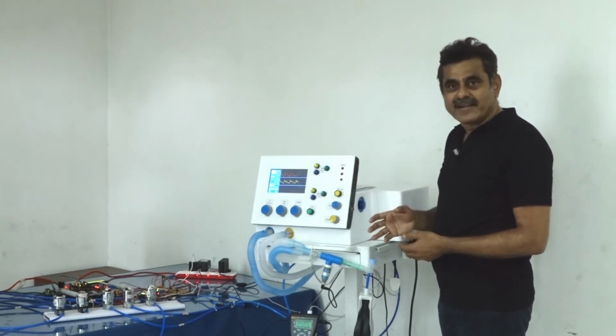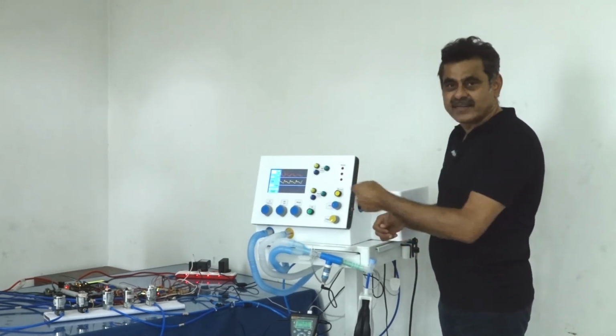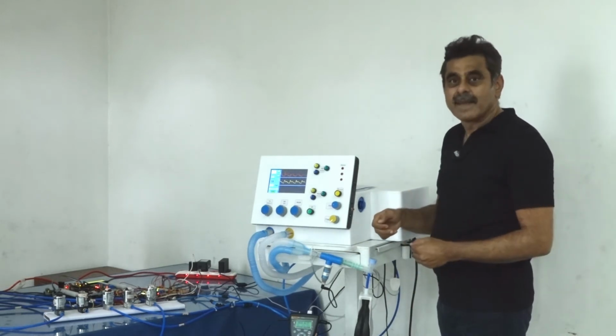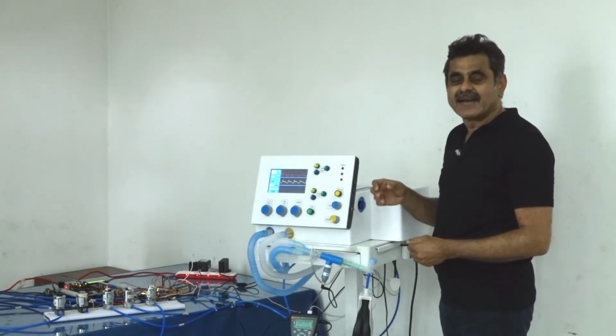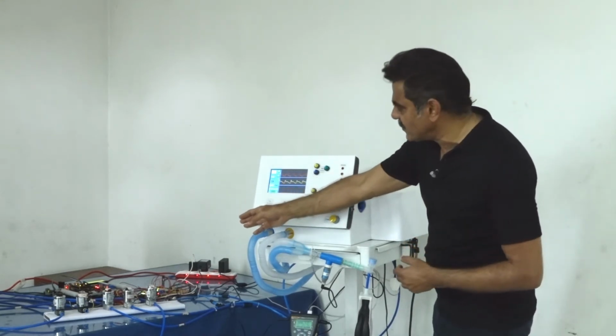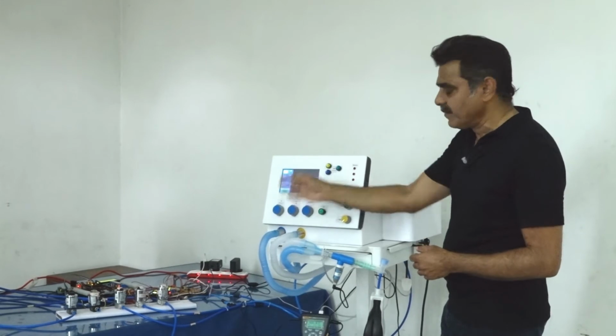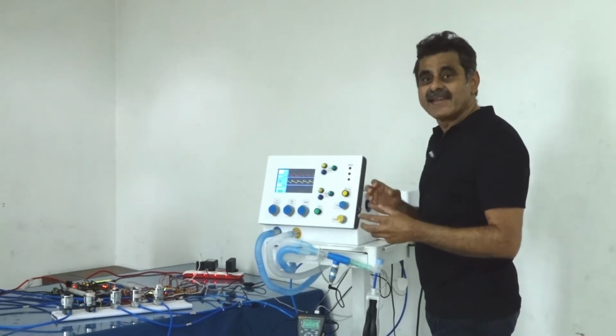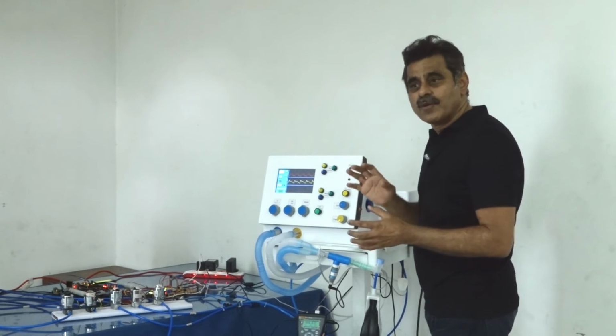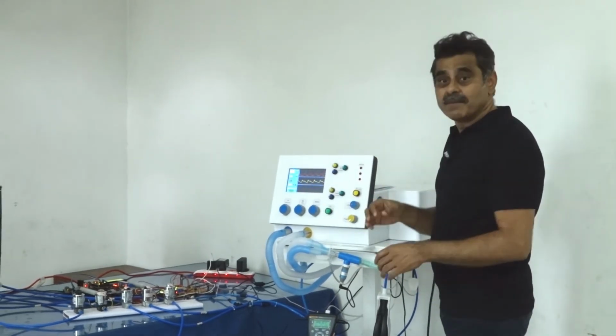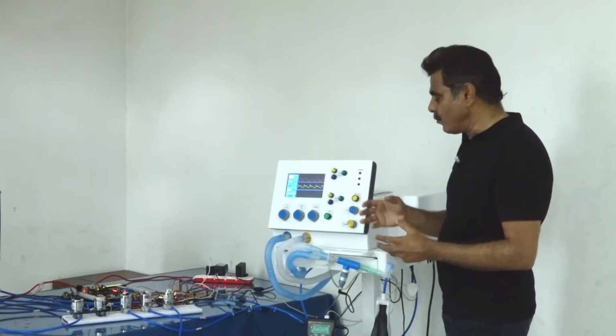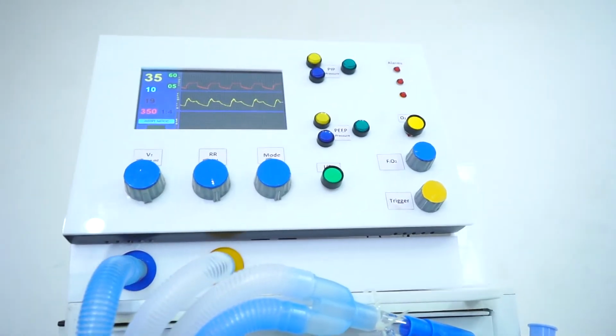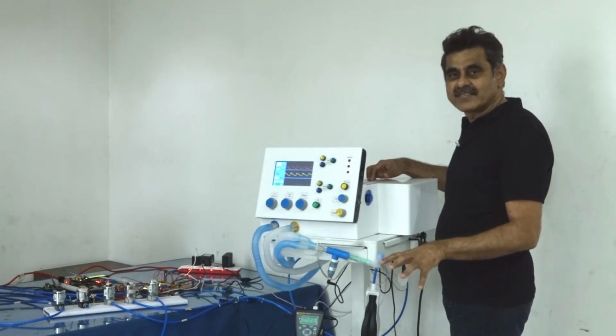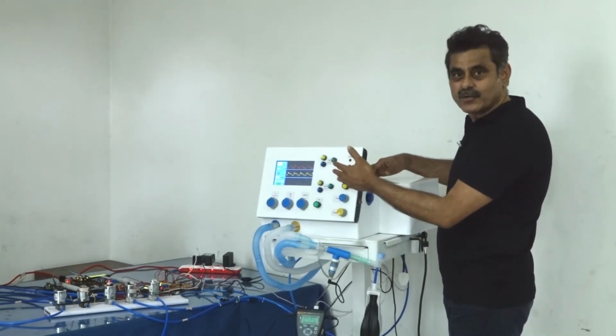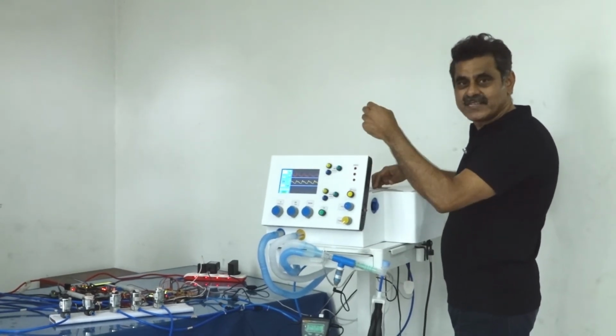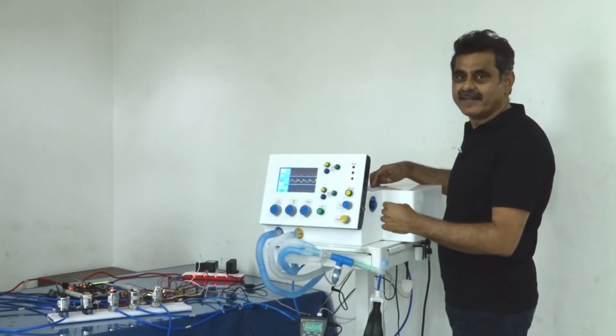Now, the low end ventilators, instead of touch screens, will have knobs and mechanical settings, and instead of the highly sophisticated pressure sensors you see there, you can use manual manometric settings. So you can go from manometric settings to high-end sensors, but not so high-end that they are not available. They are available all over India. While there are 3 models of ICoVent, from the lower end with manual manometric settings to the higher end with electronics, touch control and knob settings, the precision of the most expensive and the cheapest is identical.